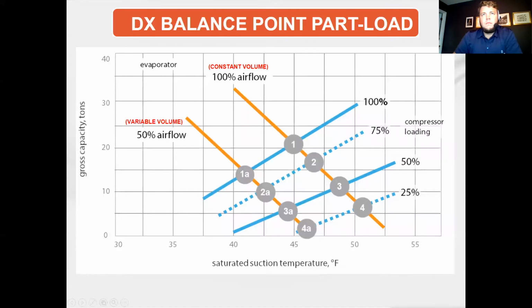Okay, so point number 1 is the balance point we just discussed, where the two curves cross. And what the right-hand curve is showing you is that in a constant volume system, when we turn compressors off, this example would show you a 20-ton unit with four 5-ton compressors in it. So at point 2, we've turned off one compressor, and the suction pressure has gone up a little bit because the capacity has gone down a little bit.